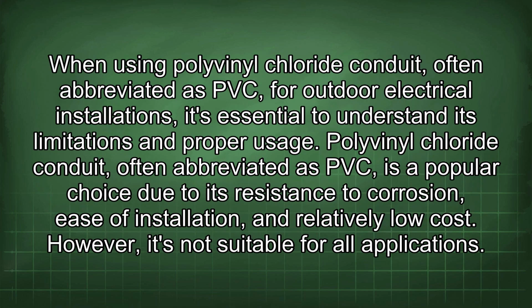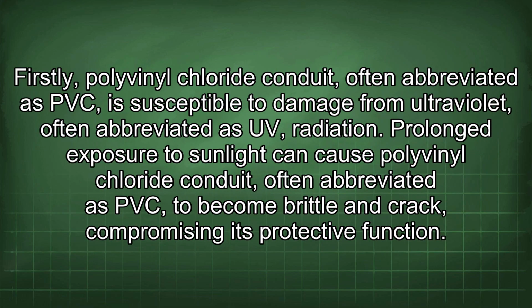When using polyvinyl chloride conduit, often abbreviated as PVC, for outdoor electrical installations, it's essential to understand its limitations and proper usage. PVC is a popular choice due to its resistance to corrosion, ease of installation, and relatively low cost. However, it's not suitable for all applications. Firstly, PVC is susceptible to damage from ultraviolet, often abbreviated as UV, radiation.